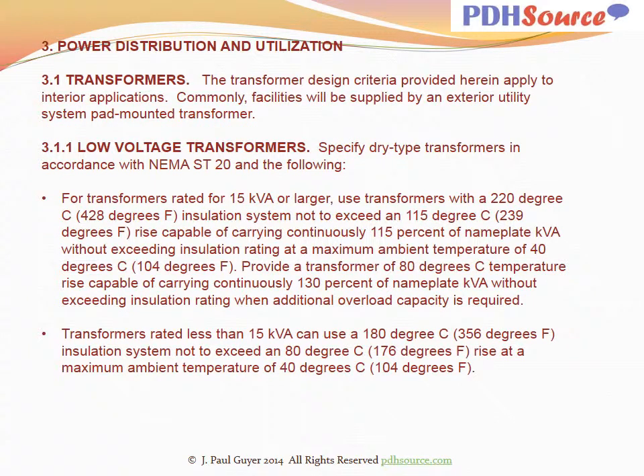Transformer design criteria provided here apply to interior applications. Commonly, facilities will be supplied by an exterior utility system pad-mounted transformer. With regard to low-voltage transformers, specify dry-type transformers in accordance with NEMA Standard ST20 and the following. For transformers rated for 15 kVA or larger, use transformers with a 220 degree centigrade, 428 degree Fahrenheit insulation system, not to exceed a 115 degree centigrade, 239 degree Fahrenheit rise, capable of carrying continuously 115% of nameplate kVA without exceeding insulation rating at a maximum ambient temperature of 40 degrees centigrade, 104 degrees Fahrenheit.